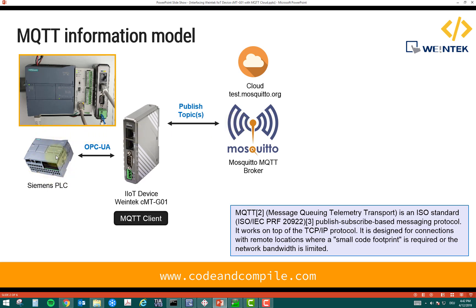Publishing a topic means whatever information I want from my PLC — such as temperature or level — I can push to the cloud. This will be sent as a published topic. For testing the cloud, I'm using test.mosquitto.org, so my information will go to this server. My IoT device is also capable of subscribing to a topic, meaning it can read information from the cloud, and I can use that information in this PLC or another PLC.